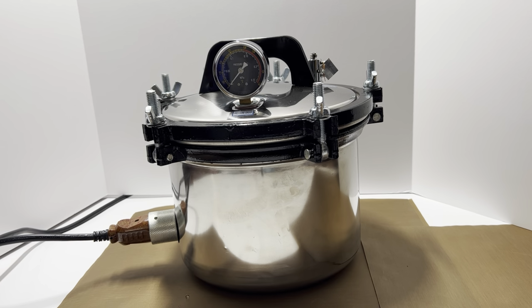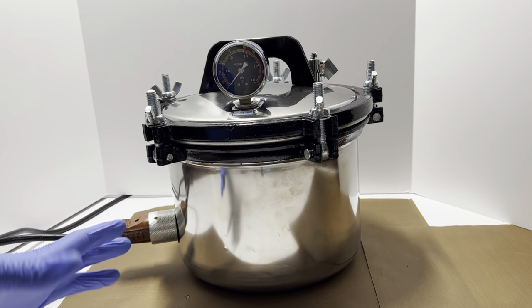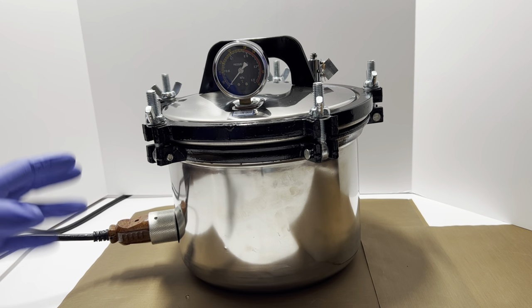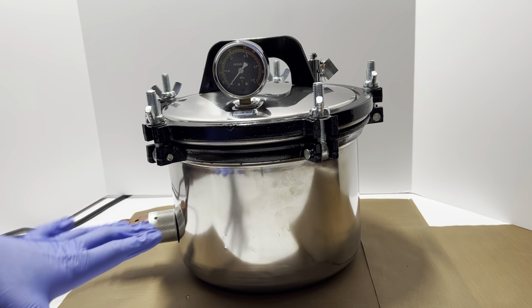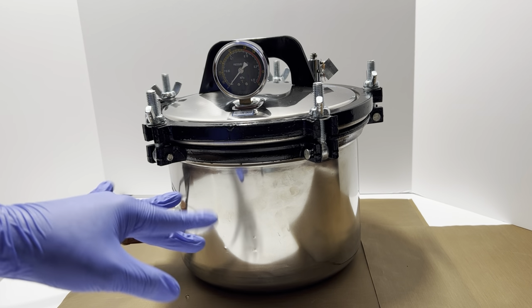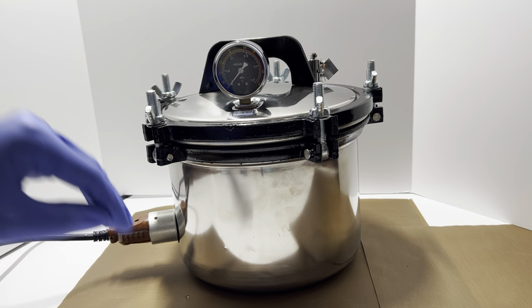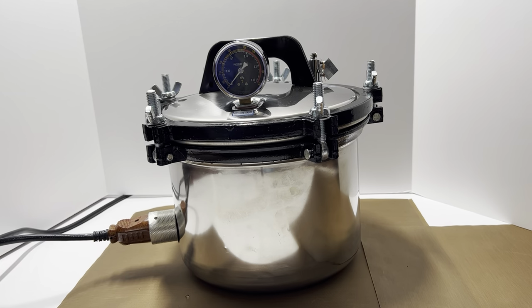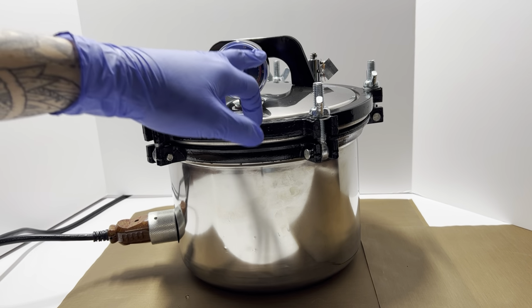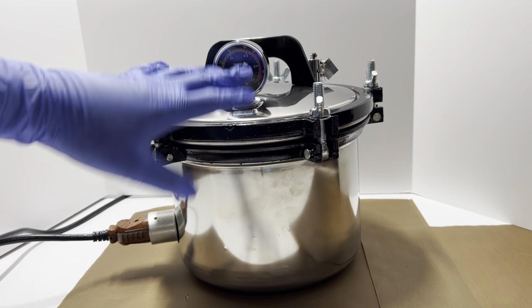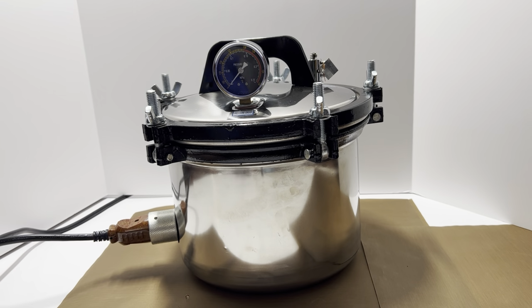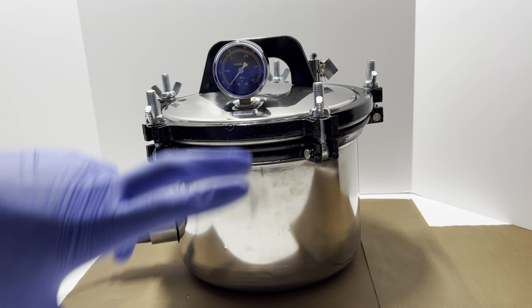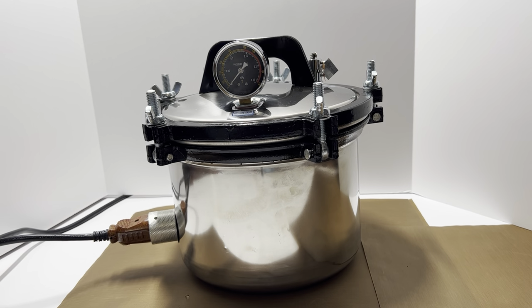With that being said though, I'm allowing this to heat up. It's going to take maybe a few moments. I don't know exact time frames, but it's going to start heating up. And then from when I hear the water actually coming to a good boil is when I more or less begin the sterilization process. It's going to start rising in temperature, and that's when the water is actually working. So essentially, when everything is working is when, for me, the sterilization process begins.